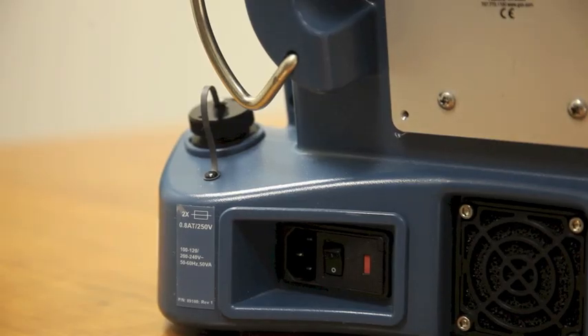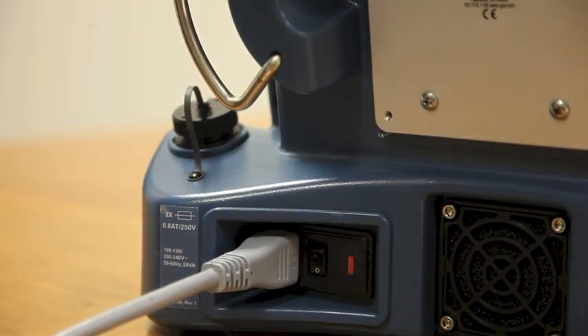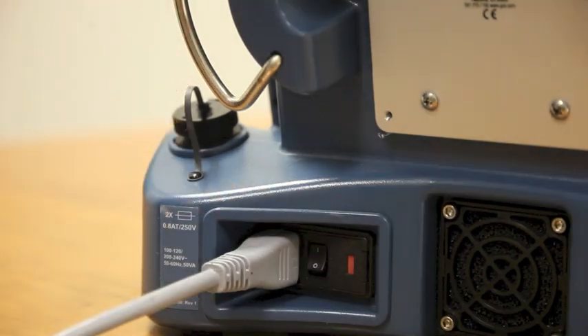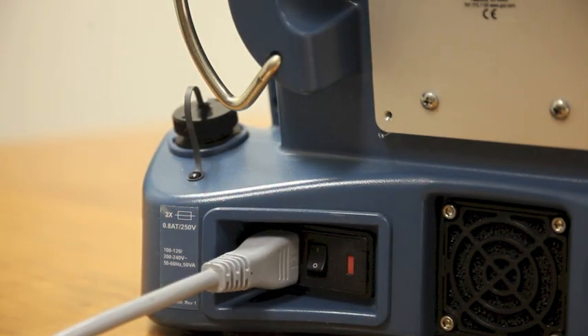Make sure the power cord is firmly connected in the rear of the console. The power switch located on the back side should be in the up position towards the 1. The backup battery in the monitor lasts approximately 30 minutes and is designed for transport use only. The console should be plugged in at all times while in use.